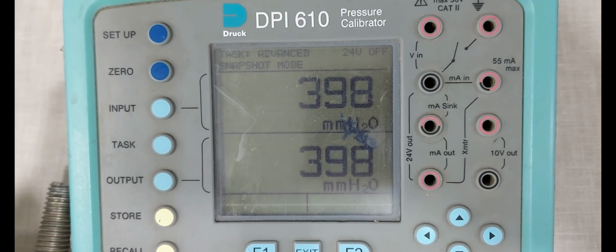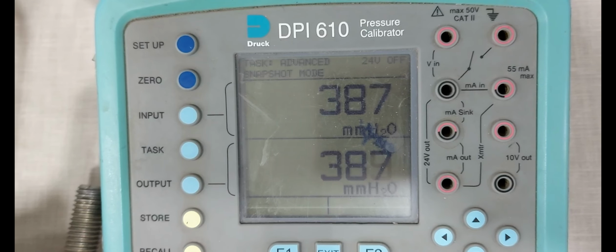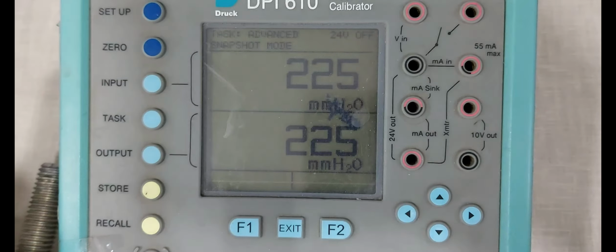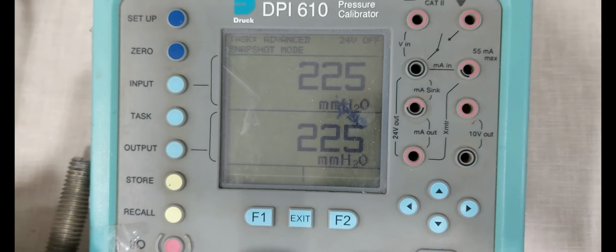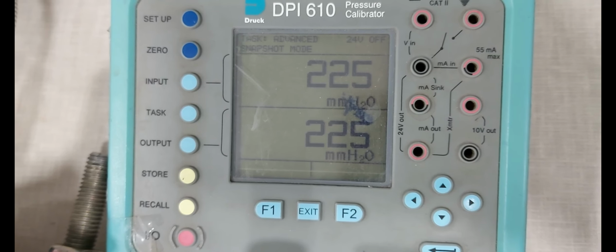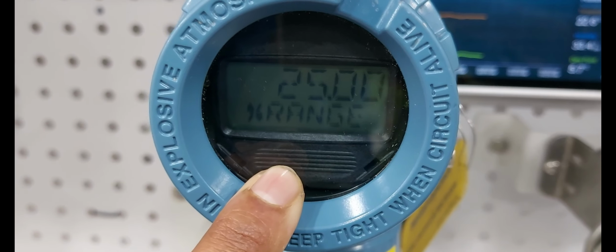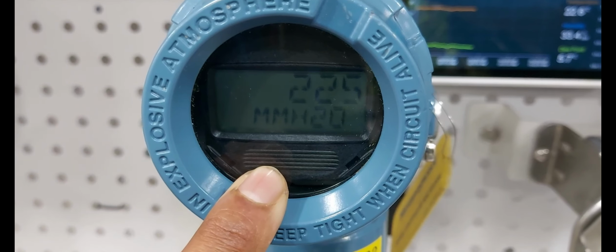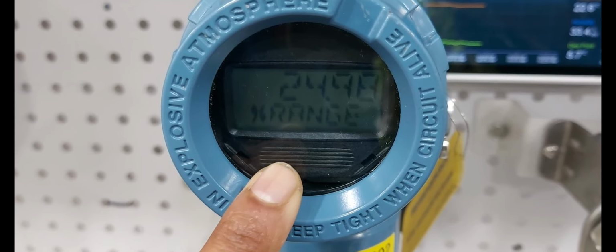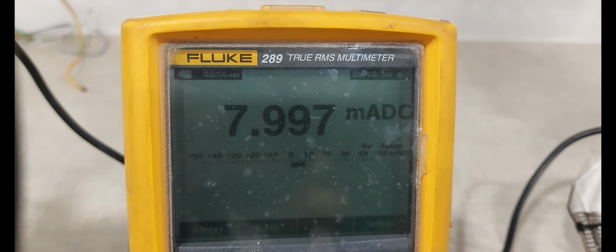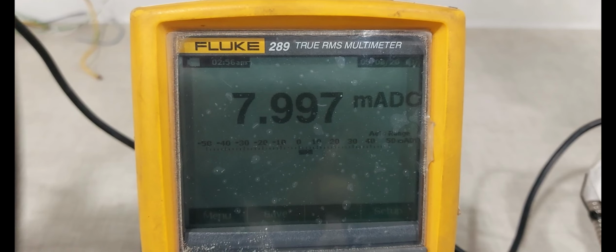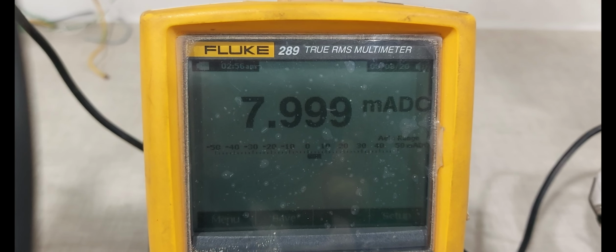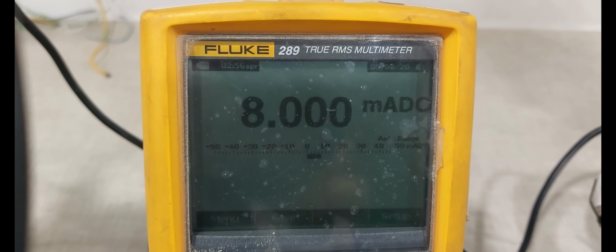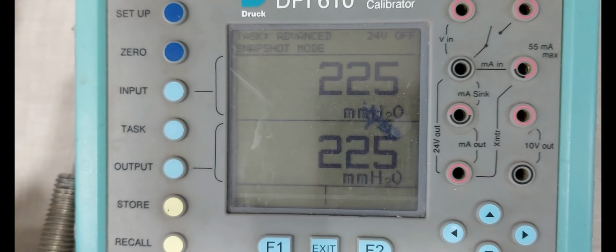Next we are moving into the 25% value. Now 225 mmH2O almost reached in the pressure calibrator. Now transmitter display showing 25%, 225 mmH2O. Now transmitter output is showing 7.999. Now almost reached 8 milliamps.